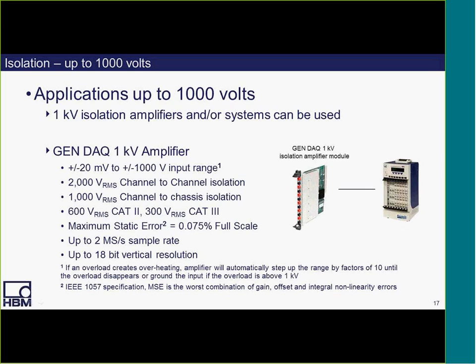So here we have an excellent solution to connect and acquire all the high power signals in efficiency testing, as an example, or any high-power application incorporating voltages up to plus minus 1,000 volts. What we have here is an HBM GEN DAQ 1 kV amplifier, and it has an input range of plus minus 20 millivolts up to plus minus 1,000 volts. And you see the number one there next to the word range.